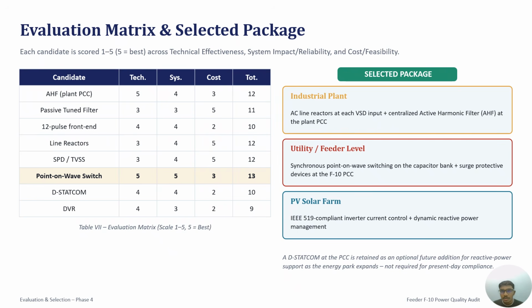And one more decision was worth noting. We retained the STATCOM at the PCC for the energy park expansion, but it isn't required for present day compliance.